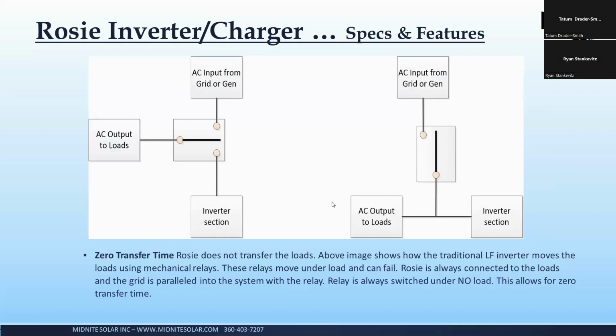On a high frequency inverter, the loads never move. The loads are always connected to the inverter. All that relay does is parallel in the utility grid or generator, and it does that at absolute zero load. So because we control that, we match the grid 100% in voltage, frequency and phase. We close the relay at zero load.